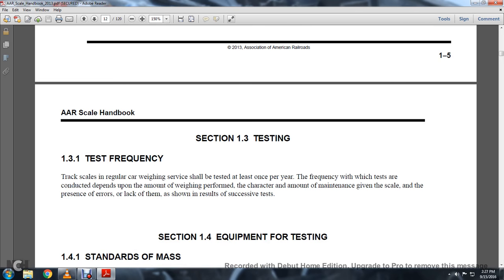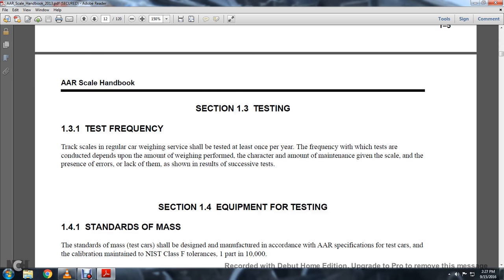Section 1-3: Testing. 1-3-1: Testing Frequency. Track scales in regular weighing service shall be tested at least once a year. The frequency with which tests are conducted depends upon the amount of weighing performed, the character and amount of maintenance given to the scale, and the presence of errors or lack thereof shown in the results of successive tests.